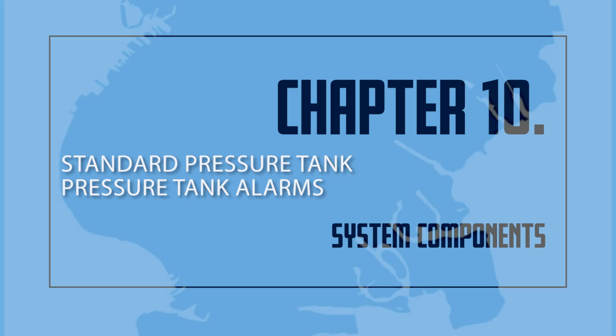The alarm system automatically monitors the air-to-water volume ratio, which should always be 1 air to 2 water. An alarm signals the certificate of fitness holder or central station operator when the water level or the air pressure rises too high or falls too low. When this occurs, the pressure tanks should be adjusted or repaired immediately.